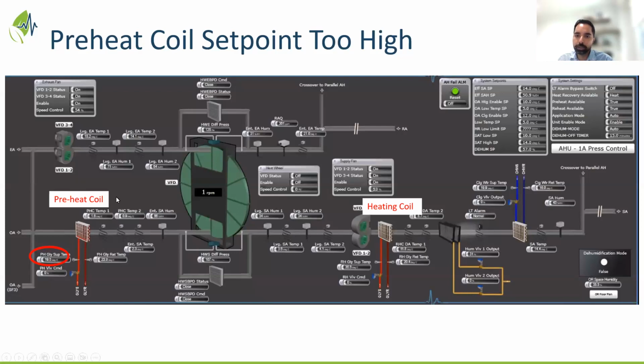However, like the recommendation that you see in certain facilities, because they're older, they have a different infrastructure. So we're recommending an approach where you're incrementally reducing the supply preheat set points lower, so you can look at the limiting factor in your existing systems.